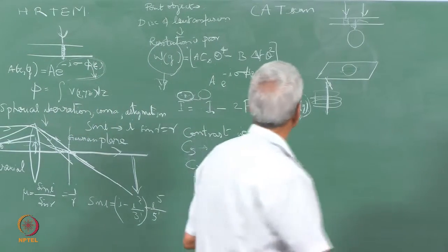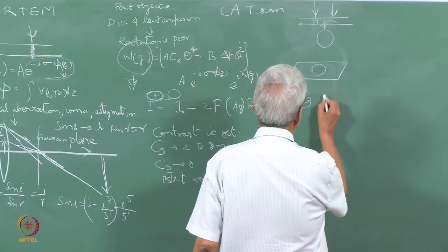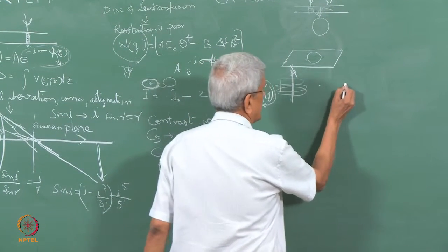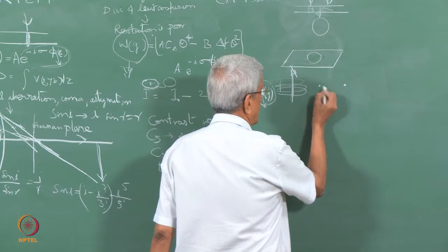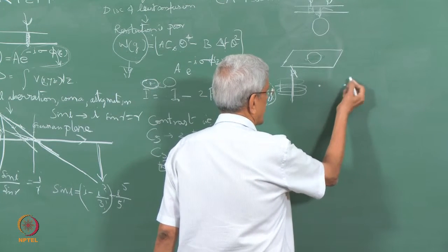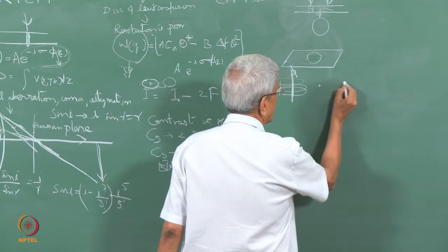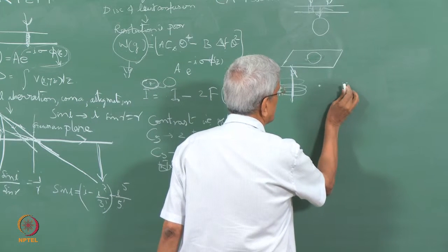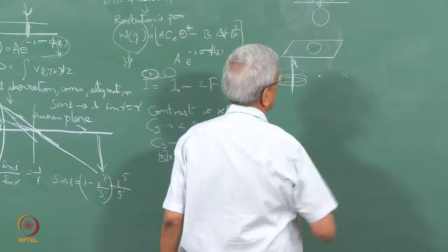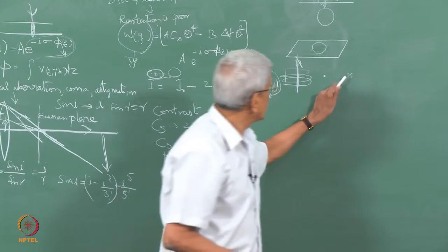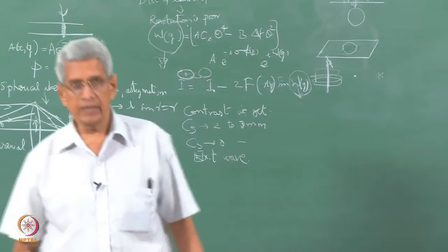The consequence of this scattering is that, if this is the central spot and we get a diffraction spot here in a non-magnetic sample, then suppose the sample undergoes some magnetization when we are viewing it or lower the temperature. This spot will essentially split into a few, depending upon the type of domains and the direction of the magnetization. Now we can put an aperture around each of these parts and image the magnetic domains.